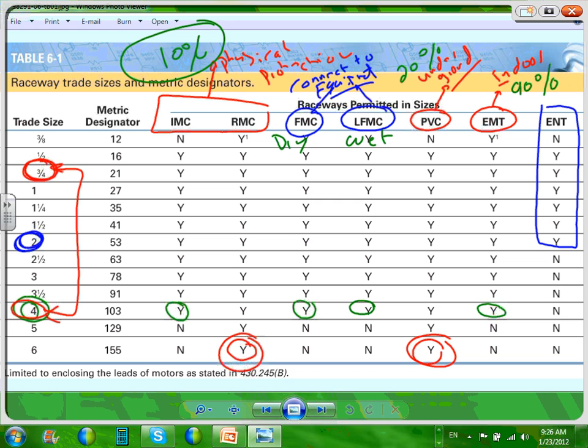Literally, they make a PVC coated RMC. They call it PVC coated RMC. They have a rigid metal conduit and they coat it with PVC. Why would they coat it with PVC? Because of corrosion. So this baby handles corrosion as well as interference. I don't know if you can read. Corrosion as well as interference. Radiation labs, anything that needs to minimize interference.